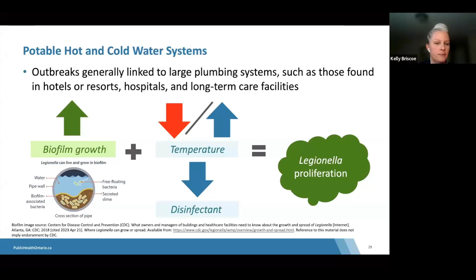There can also be redundant pipe work or dead legs or dead ends that can allow for water stagnation. And stagnation can also be affected by water use or intermittent water use and the type of setting. So consider for a moment water distribution in a small private home compared with a hotel that's at a capacity of 50%. So these would be very varying flows of water throughout the system. Hot weather can also influence the incoming water temperatures, particularly when water is provided from a surface water source. So all of these characteristics together encourage biofilm growth and reduce temperatures and levels of disinfection, which can all lead to Legionella proliferation.